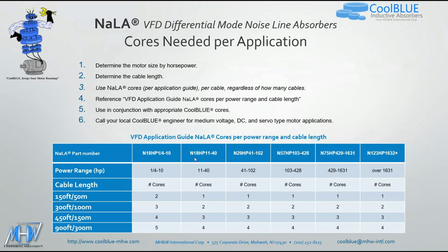The NALA, which is the differential mode line absorber, is a core that goes on each individual line. So in most applications, you're going to need a minimum of 3 of these. Again, it's the same scenario. You look at the motor size by horsepower, you look at your cable length, then you use the NALA application guide to figure out exactly which core part number you need and how many. So in that same 75 horsepower system, here's your part number for the NALAs. For 150 feet of cable, you're going to need just 1 NALA, times 3 for your 3 phases. So you'll need a total of 3 NALAs, the N29HP41-102.